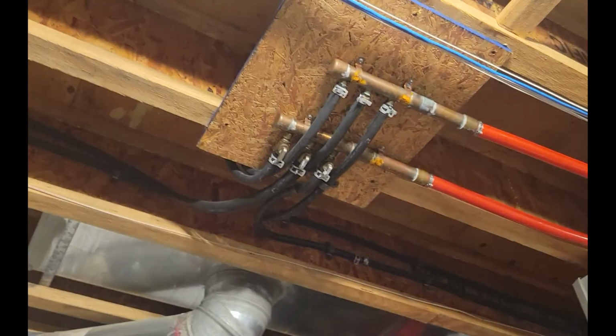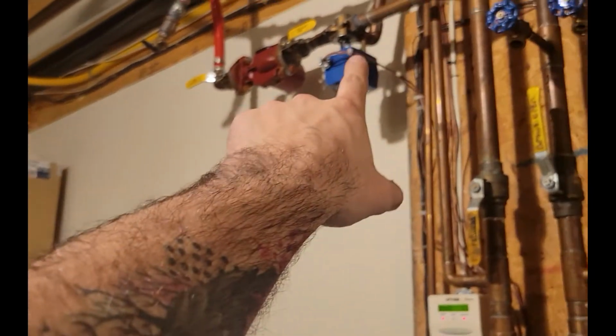Oh, it's got the old black tubing right there, that's actually non-oxygen barrier tubing. There's been a lawsuit on that tubing. That's not good, because that tubing forms a lot of debris on the inside of the pipe. It has no oxygen barrier, so you get a lot of issues with that, like those components clogging up a lot.